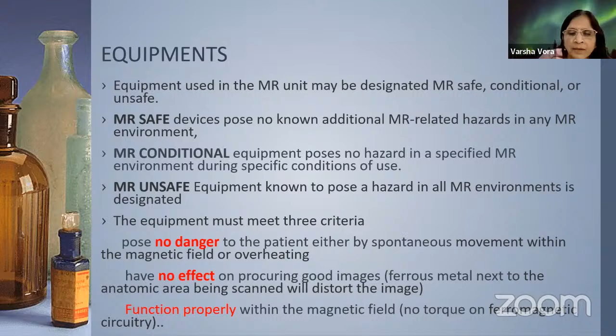The equipment must meet the 3 criteria. Pose no danger to the patient either by spontaneous movement within a magnetic field or overheating. Has no effect on procuring good images; ferrous metal next to the anatomic area being scanned will distort the image. Functions properly within the magnetic field, no torque on ferromagnetic circuitry.